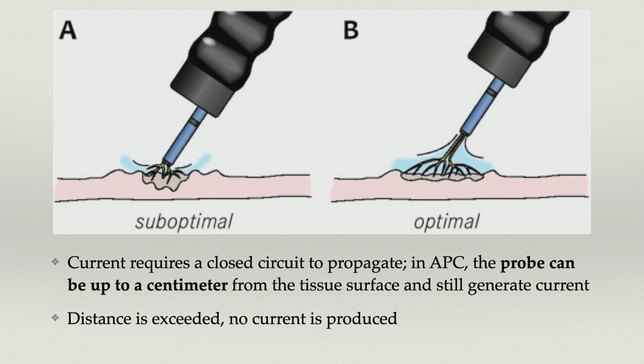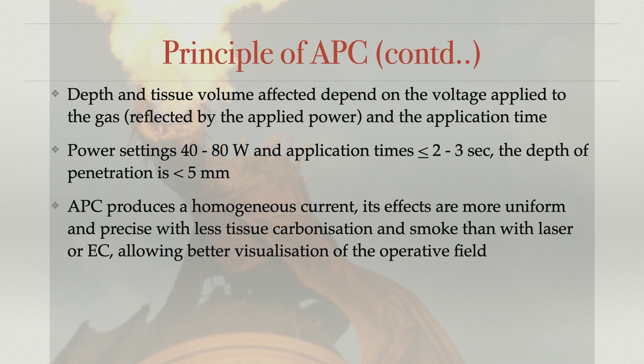Of course, you require settings of 40 to 80 watts. So just remember that we are not using too high a temperature. The pulses are only for 2 to 3 seconds and the depth never goes beyond 5 millimeters. So you can't inadvertently cause a deep burn in such situations. It's usually only the superficial burns, and over a period of time this sloughs off, and therefore the tissue becomes better with time.